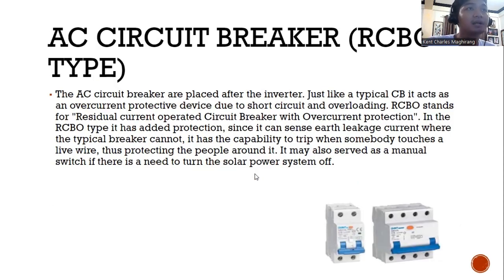The AC circuit breaker is placed after the inverter. Just like a typical CB, it acts as an overcurrent protective device against short circuit and overloading. RCBO stands for Residual Current Operated Circuit Breaker with Overcurrent Protection. In the RCBO type, it has added protection since it can sense earth leakage current, which a typical breaker cannot. It has the capability to trip when somebody touches a live wire, thus protecting people around it. It may also serve as a manual switch if there is a need to turn the solar power system off.